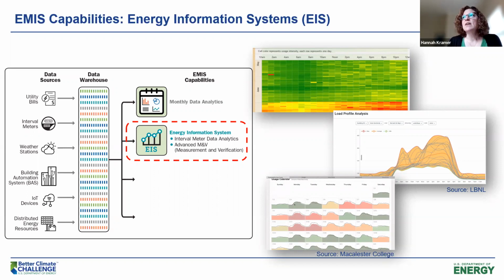Then there's a predictive process where you look at the prediction of energy use at every hour, and the tools automatically do this based on models. In the bottom graph, if your actual energy use is less than or equal to the prediction, you're doing good. But on a day where actual use is greater than the prediction, you'll see a gap between the two and that day shows as red. So you can start to see patterns, like maybe Mondays are always hard, or a holiday where you didn't turn down the systems. You can program in different schedules as well.